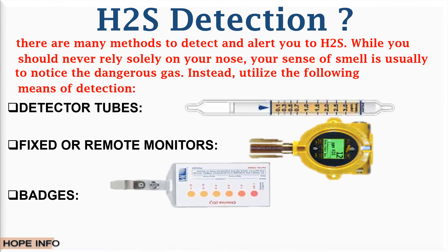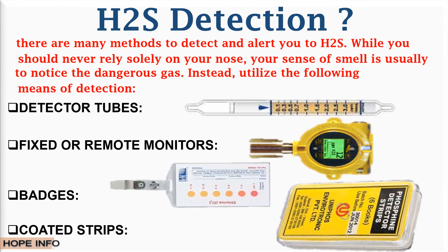Detection method number three is badges resembling credit cards — these portable monitors can be carried and change color depending on gas level; some can also set off an alarm if exposure exceeds a set level. Detection method number four is colorimetric strips: lead acetate strips that usually turn brown or black due to H2S, with the degree of color indicating the gas concentration. While helpful for determining if H2S is present, colorimetric strips should not be the only tool used, as they are not fully accurate. Work sites should utilize various tools together to detect H2S.